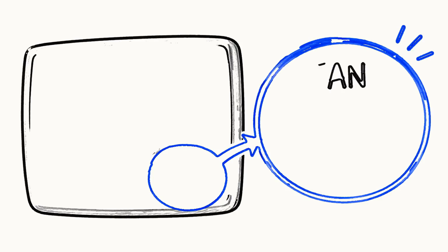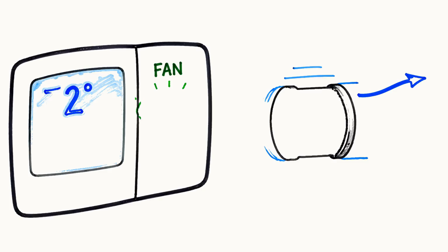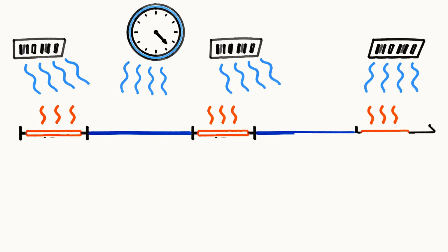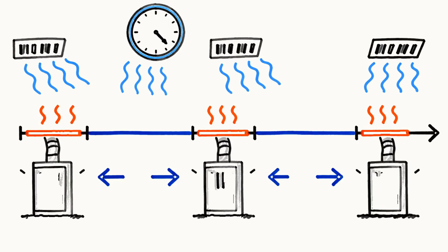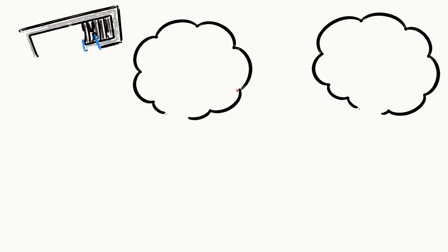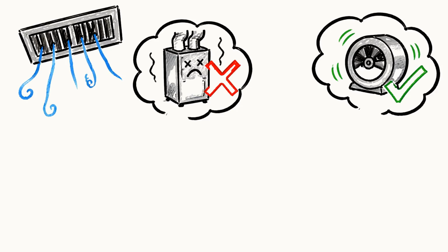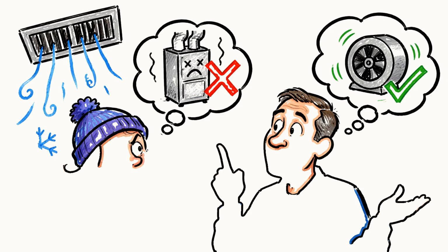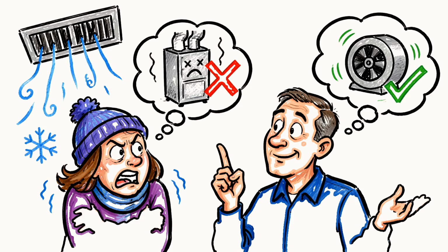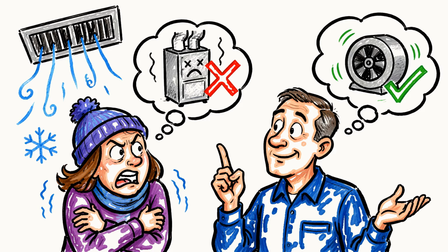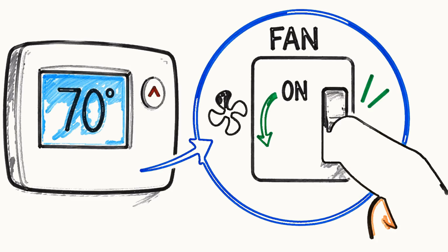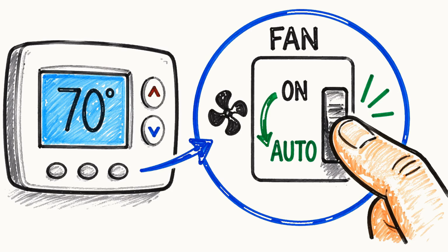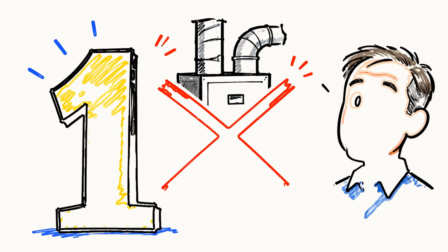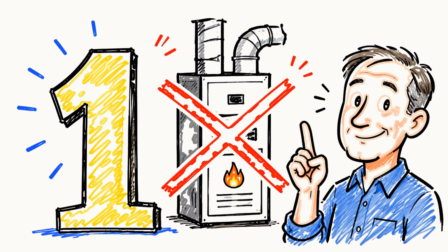The second thing that fools people lives on your thermostat. Look at the fan setting. If it is set to on instead of auto, the blower runs all the time, including the long stretches between heating cycles when the furnace is not making any heat at all. That moving room temperature air feels cold coming out of the vents, and people swear their furnace is broken when really the fan is just doing exactly what they told it to do. Switch that fan setting to auto so the blower only runs when the furnace is actually heating. This single setting is the most common reason people think their furnace died when it did not.